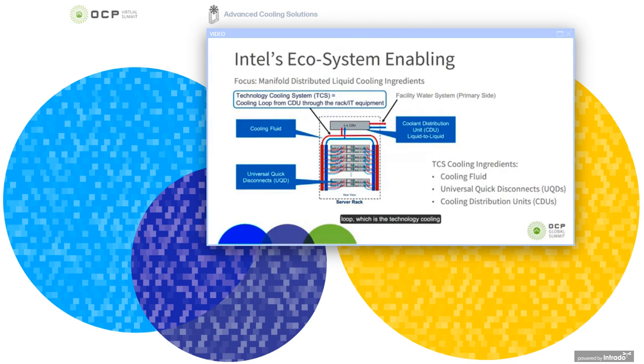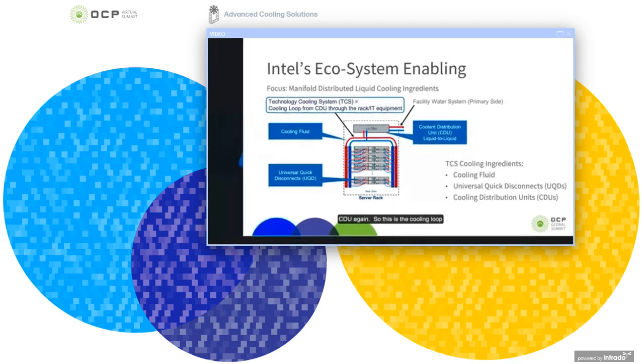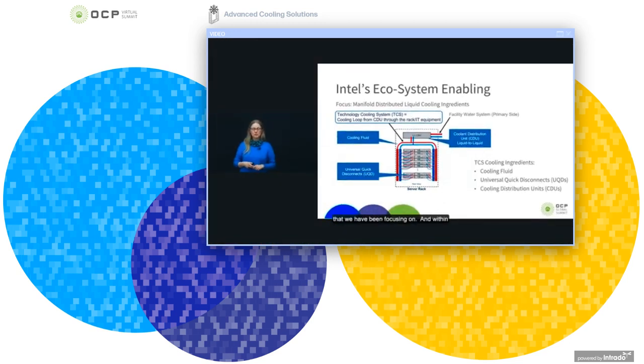So within Intel's ecosystem enabling, we're focusing on the manifold distributed liquid cooling ingredients, and specifically the TCS loop, which is the technology cooling systems loop. And this cooling loop goes from the CDU, so the coolant distribution unit, through the rack manifold, through the IT equipment, to the return manifold, and back to the CDU again. So this is the cooling loop that we have been focusing on. And within that cooling loop, we have 3 different ingredients that we have been investigating. And those are the cooling fluid itself, the coolant distribution unit, liquid to liquid CDU, and then the universal quick disconnect, or the UQD as we're calling it.